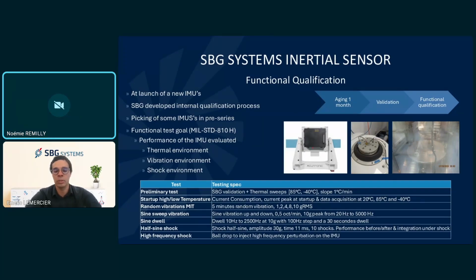Then we also look at the shocks. For the shock, we have 2 types of tests. One test is the half sine, which is 30 G with a duration of 11 milliseconds and 10 shocks, to evaluate performance before and after shocks, and even under shocks. And the other one is the high frequency shock, where we use a ball drop to inject high frequency and see if there is any perturbation on the output of the IMU data.